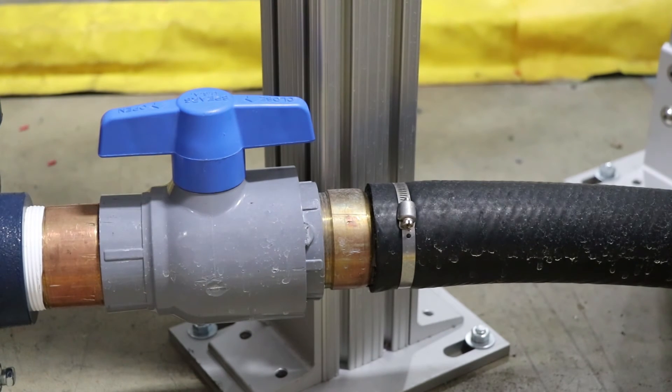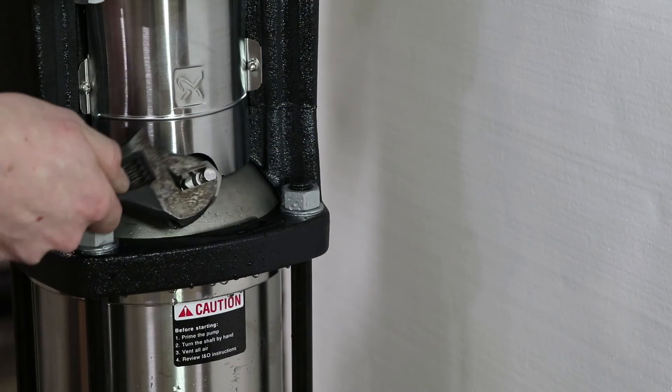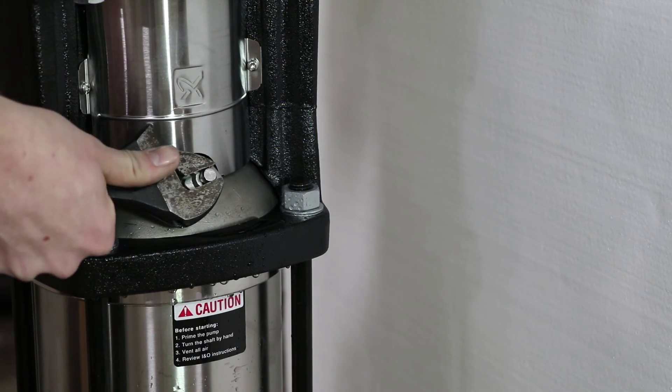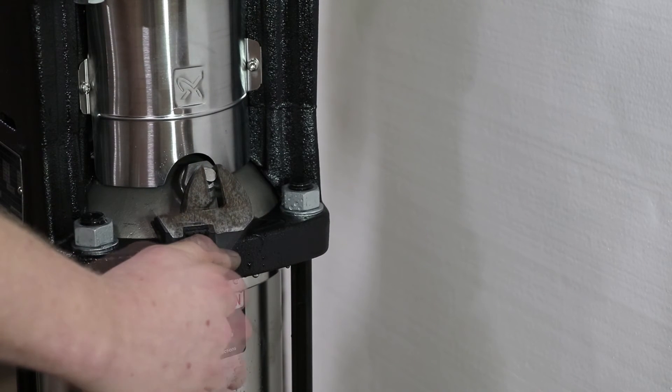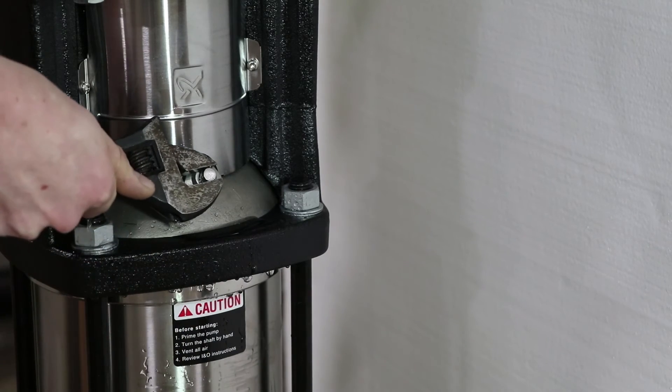After this process remember to re-prime your pump. To re-prime your pump use an adjustable wrench to open the vent at the top of the pump stack. You'll hear air hissing out for a little while until water starts to flow out. Once water starts to flow out you can then tighten to close.